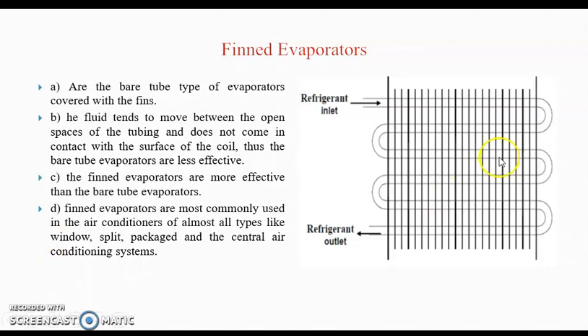Since the fins increase the contact surface for heat transfer, the finned evaporator is also known as the extended surface evaporator. This type of finned evaporator is primarily designed for air conditioning applications where the refrigerant temperature is above 0 degrees Celsius. The finned evaporator should never be allowed to frost, because accumulation of frost between the fins reduces capacity. The gap between the fins is very small, about 3 mm.